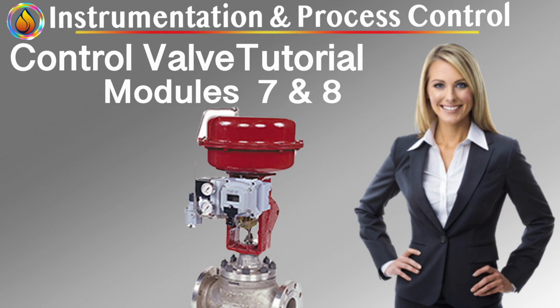Shaft windup and backlash. In rotary valves especially, mechanical elasticity matters. Shaft windup, torsional deflection under load, causes delayed motion and introduces phase lag. Backlash, lost motion due to mechanical clearances, causes asymmetrical response and degrades repeatability. These effects mean that actual flow change may lag position feedback, confusing the controller and degrading loop stability.